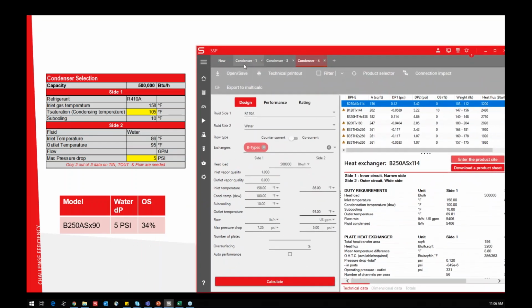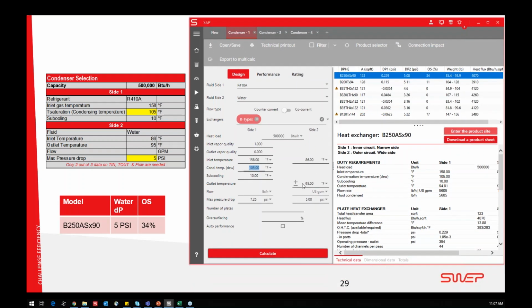So if we go back to calculator number 1, let's say you just want a basic condenser, 105 Fahrenheit condenser, you don't care so much. What you could do to reduce the number of plates is accept a higher pressure drop. Let's go up 1 psi and see what happens. From 90 to 80 plates, we changed that by 10 plates. That was pretty good.